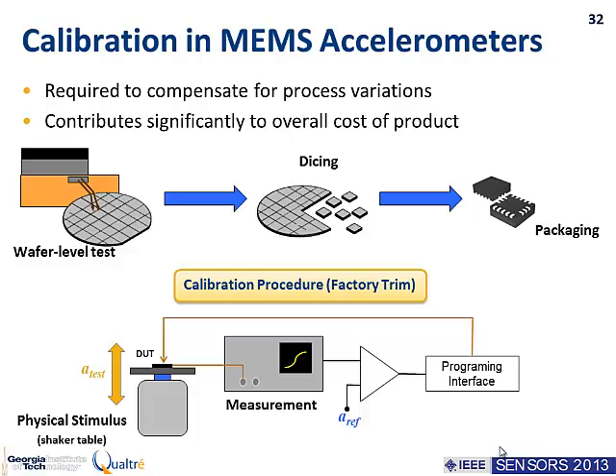The typical way of doing this is by placing part by part on equipment that can produce a physical stimulus. For example, in an accelerometer, we put this on a shaker table, measure the scale factor, compare it with a reference, and if that scale factor doesn't meet what your product has to deliver, we have to change the gain settings of our electronics to make sure the value is right where we want it. Obviously, if you need to do this for every single part, this is going to be very time-consuming and very expensive.